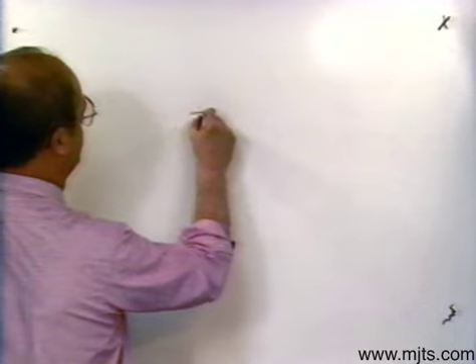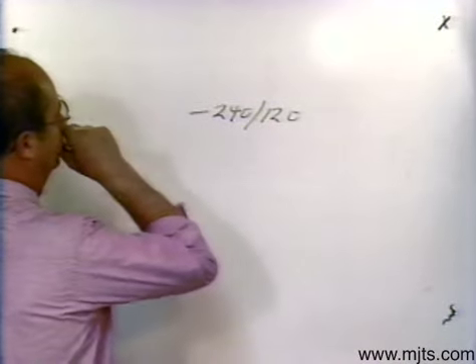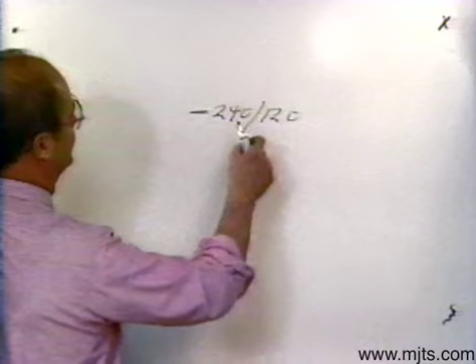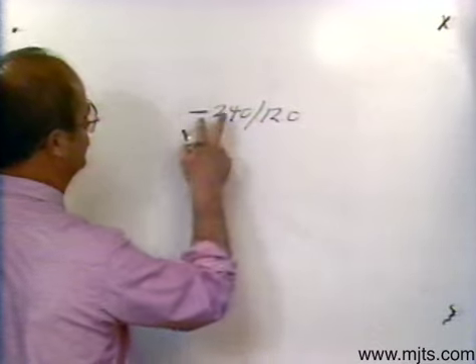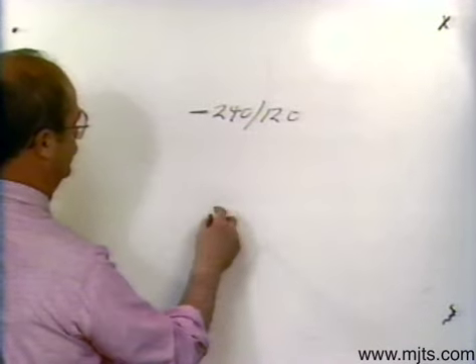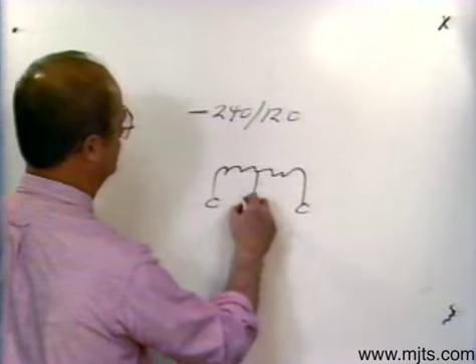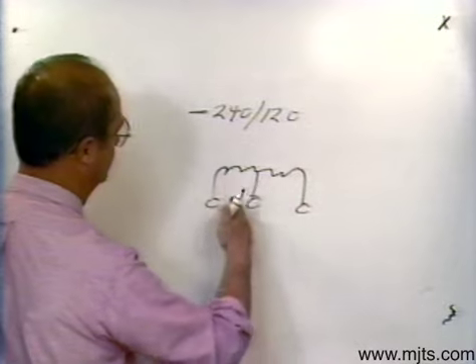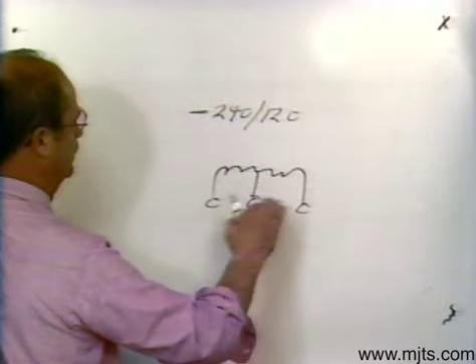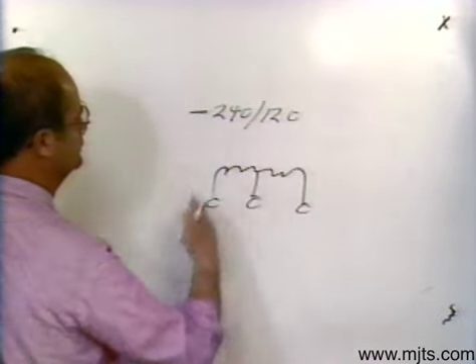The last rating I want to show you is more typical on a dry-type transformer. It's written as hyphen 240/120. You'll see the difference between this one and the other: the earlier 120/240 had a split center tap. This one has a center tap, but it's not split — it's typical for a dry-type transformer. I can't parallel it for 120 only; I'm always going to have both 120 and 240 out of that transformer. A typical high side rating here might be 480 volts.